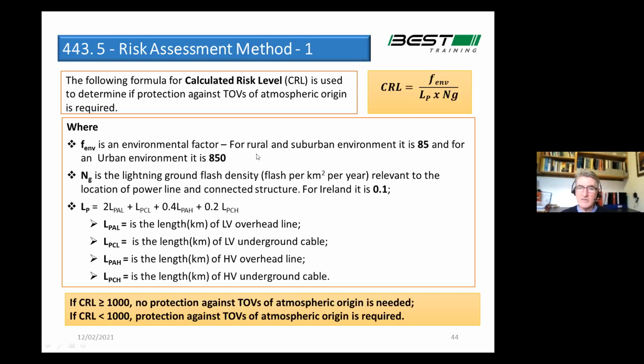But what I advise everybody doing it on the course, this is purely an assessment of the risk from a lightning strike. Most transient overvoltage damage in premises is caused by equipment within the premises and not lightning. So it's due to little transients that occur naturally in a building because of things switching on and off, photocopiers, your washing machine cutting in and out. They cause little transients to appear, and sometimes the transients can get to a magnitude that cause damage to sensitive electronic equipment. So in a nutshell, I would say don't really do this. Obviously, if you like the academic exercise, of course, go around, play around with it as I did, but I would be saying, you know, in a house, for example, an SPD is about 30 euros extra. Just put it in. It's the right thing to do.